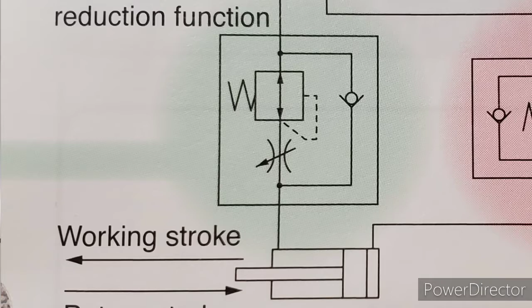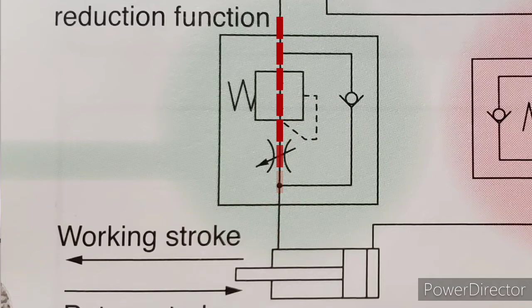You're going to put that on the side of your cylinder that is not doing work. In this example, it's on the rod side, to return the cylinder to the retracted position. Internally there is a regulator built into this speed controller, so the air is going through the regulator and the speed controller, greatly reducing the amount of air consumed on the return stroke since we're not doing work.